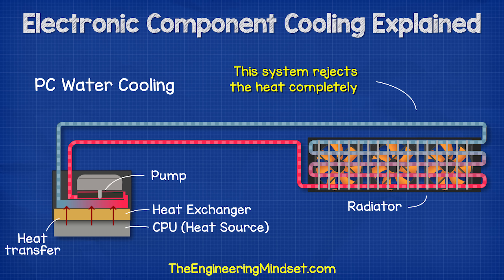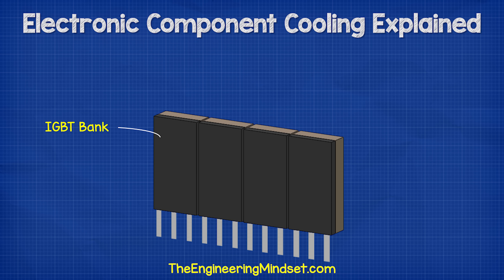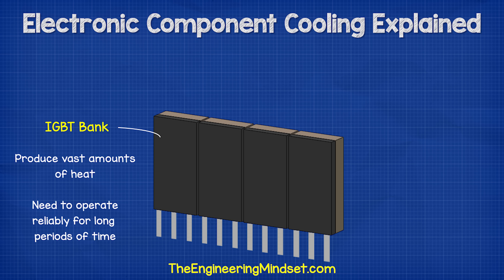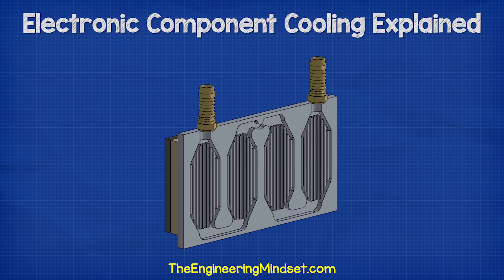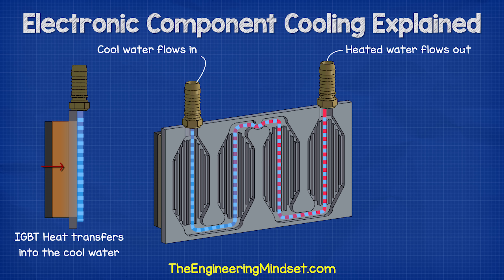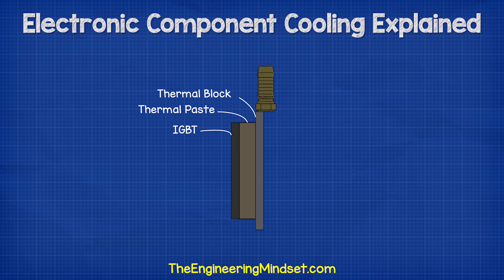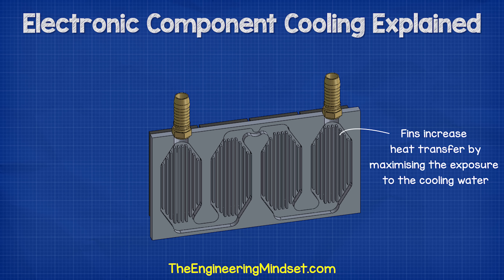This method of cooling is increasingly used in power electronics, especially in higher power applications, where we often find these banks of IGBTs. These banks of IGBTs generate huge amounts of heat and need to operate reliably for long periods of time. Instead of spacing them out like in the bench power supply, we can mount these to a thermal block — basically a heat sink or heat exchanger that water flows through instead of air. As the IGBTs generate heat, this will pass through the block and into the water. Between the IGBTs and the thermal block, we have a thick layer of thermal paste which helps to increase the heat transfer. Inside the block, we have fins to help increase the surface area and maximize the exposure to the cooling water.